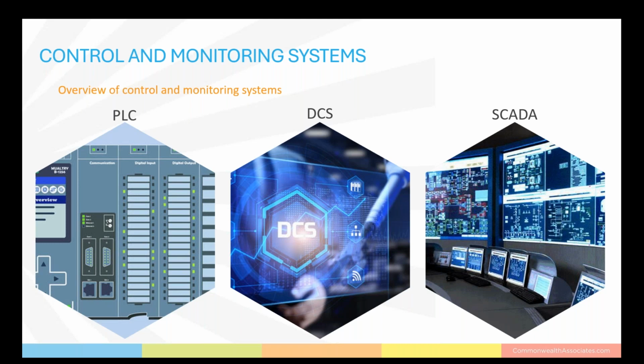One of the things that can drive overall size of the room is the type of control monitoring system. A programmable logic controller is local to individual systems, for example, burner management or turbine control. A distributed control system communicates with the local PLC controllers and balance of plant. And the supervisory control and data acquisition is the software that allows operators to see everything that's going on in the plant. There's no one layout that works for every plant. Layout and design is a conversation between plant management and the I&C engineers to find out what's preferred. And having that conversation early helps drive the size and layout of the control room.